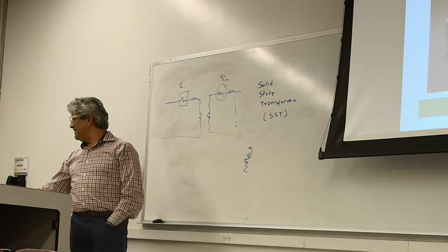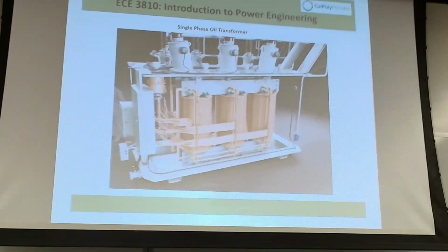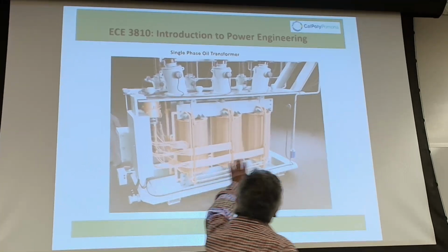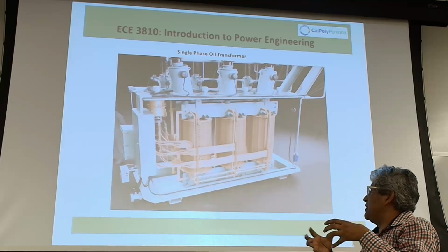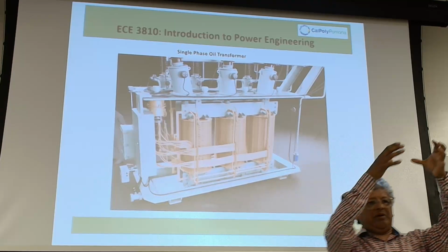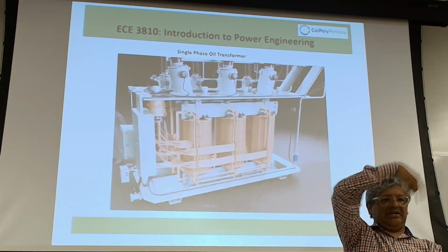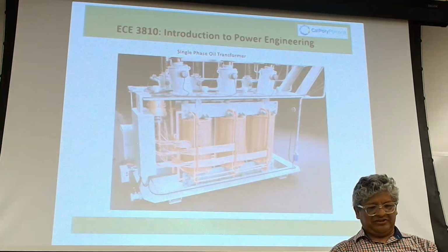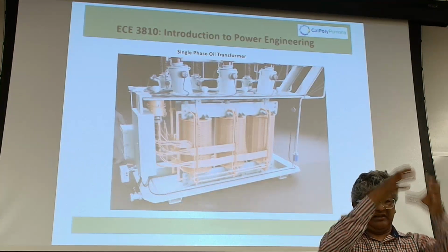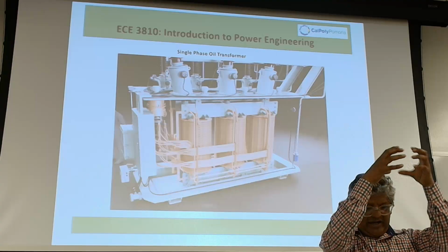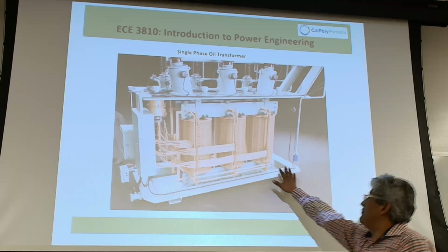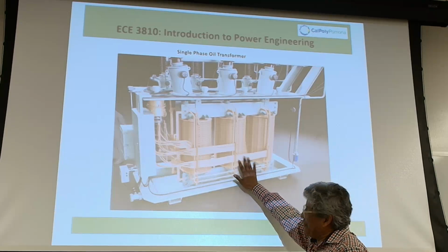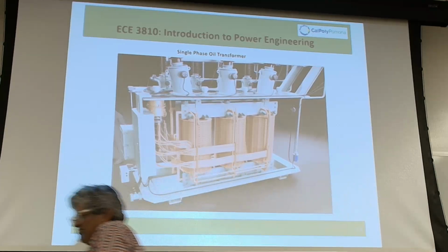The design itself is very interesting. So here are the primary and secondary phases A, B, and C. And I'll show you, there's a picture that breaks it down. They're basically cylinders: the winding here, there's a cylinder, and the winding here, there's another cylinder. So the primary and the secondary are right in between each other. They're like pancakes. For very large transformers, that's the core design.